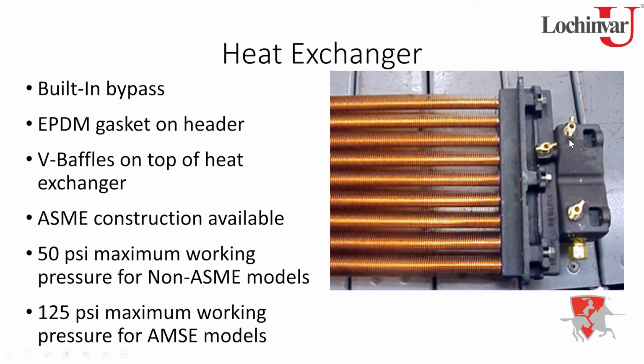I will also mention the EnergyRite is the only heat exchanger that we build today that actually has a gasket in it. So that's something you do have to remember. If you're going to have a leak somewhere, the weakest spot's typically always a gasket. Unfortunately, because of the design of the head with that bypass in there, we can't avoid that. So we do have to use a gasket on this. So just be aware of that.